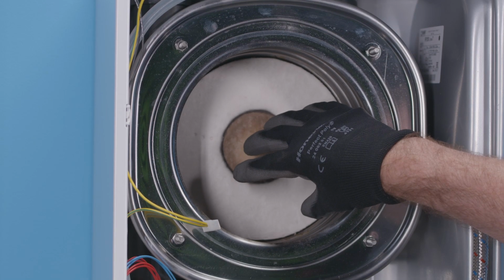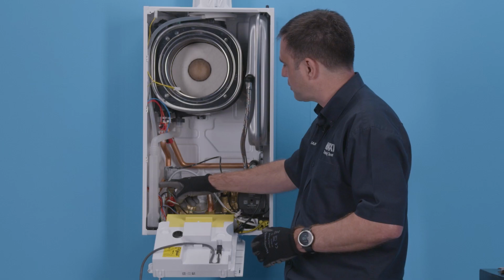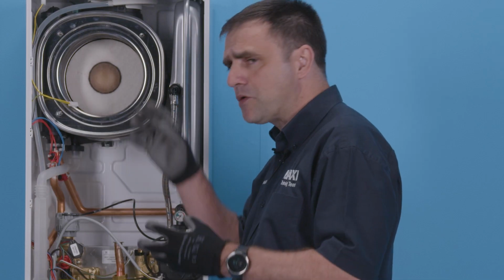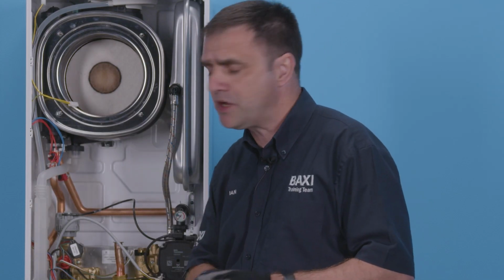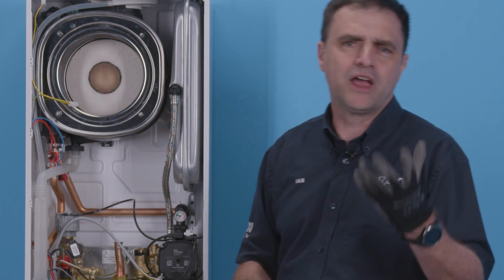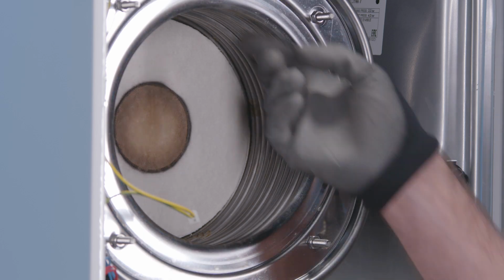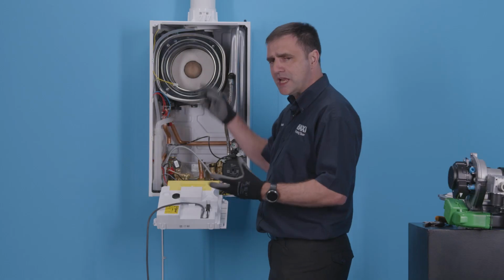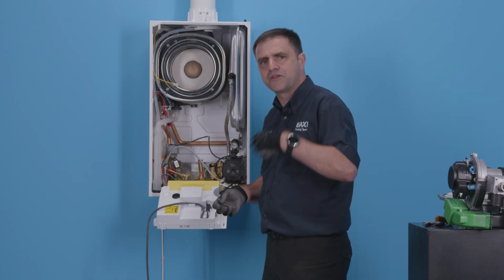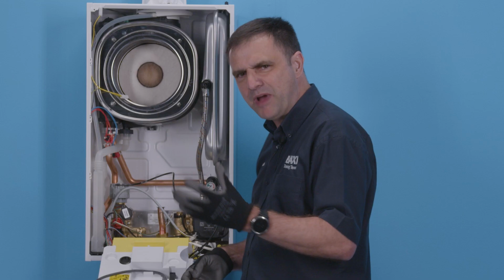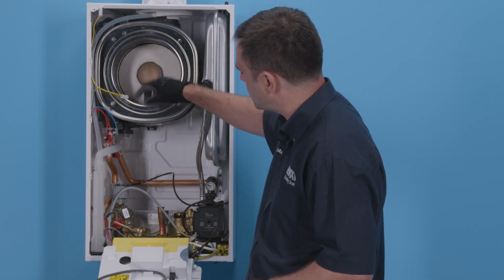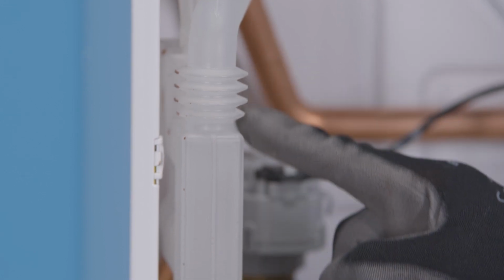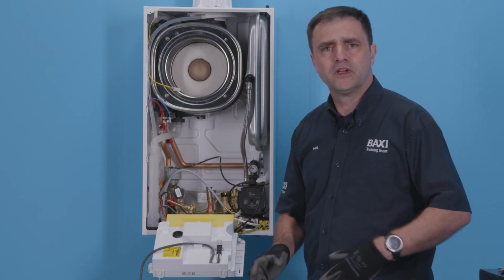Moving on to the heat exchanger, all I would do is brush around that, make sure that any debris, you can pour some water down, it'll run into my condensate trap and run away. If there was a lot of debris build up on the heat exchanger, I'd get a bottle spray of white vinegar, about a 50% solution, 50% white vinegar, 50% water. I'd spray around my heat exchanger, leave it for about 4 or 5 minutes, and then give it a brush, and again pour water down, about 500ml, down into my heat exchanger, flushing any debris out into my condensate trap, which I can then remove and flush out.